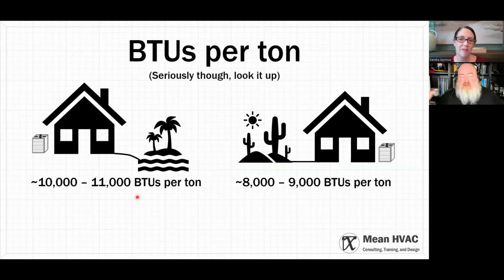There is no rule, there is no law or regulation of standards. Like they have those little verification labels on gas pumps that the U.S. Department of Weights and Measures has verified that a gallon is a gallon. Yeah, we don't have that in HVAC. Nobody's verifying a ton. I can call the system a 2-ton system and then have it not do anywhere near that. No one can sue me.